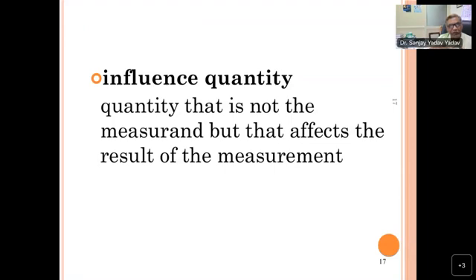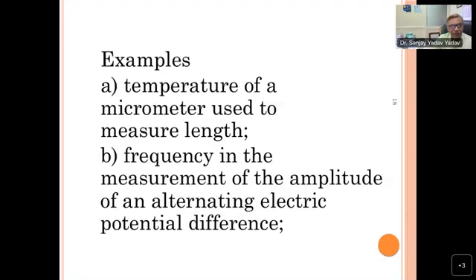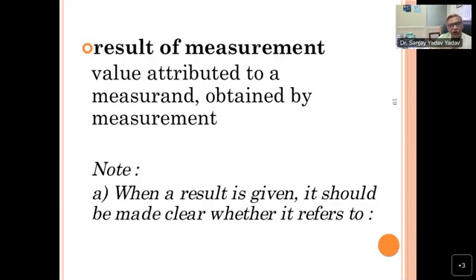Then when you are making measurement of a particular measurand, there are certain influencing quantities. So that influencing quantity affects your measurement. So the accuracy of your measurement depends upon the influencing parameters. For example, the temperature of a micrometer used to measure length, and frequency in the measurement of the amplitude of an alternating electric potential difference. And in a metallic length measurement, you can have a variation of temperature and environmental conditions. And after all this measurement process of a measurand, then you obtain what? You obtain the result of the measurement. So the value attributed to a measurand obtained by a measurement, that is the result of measurement you can get.